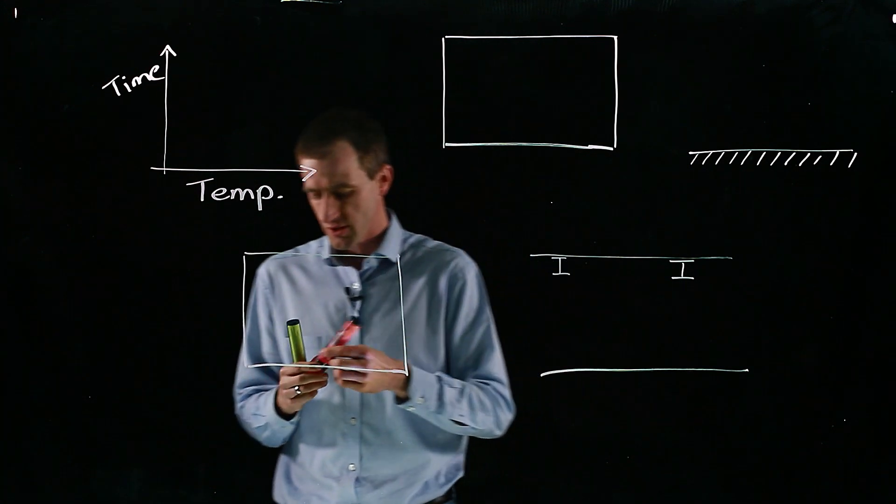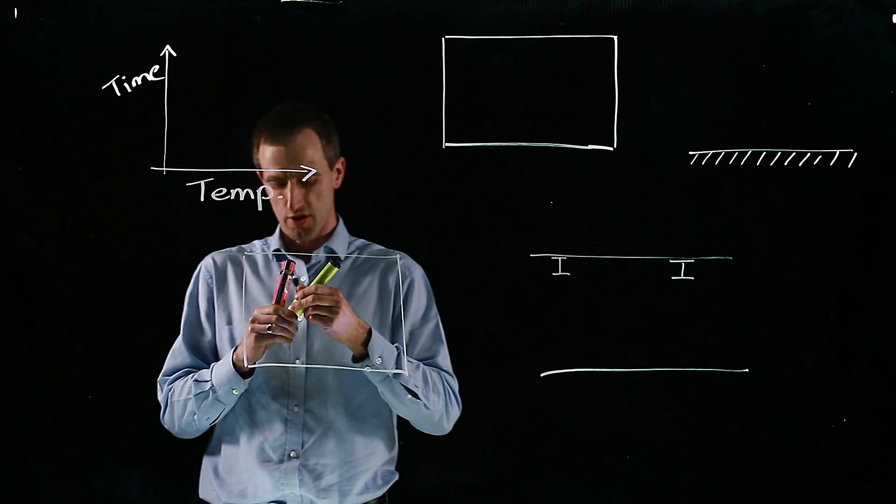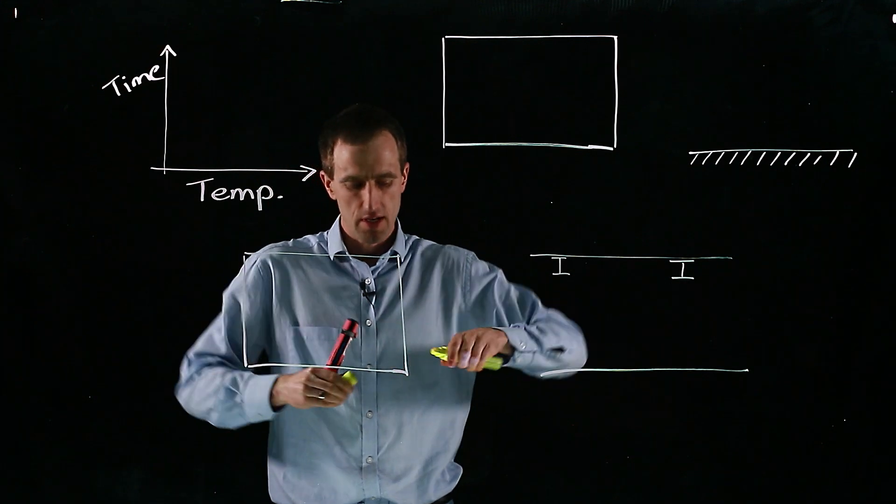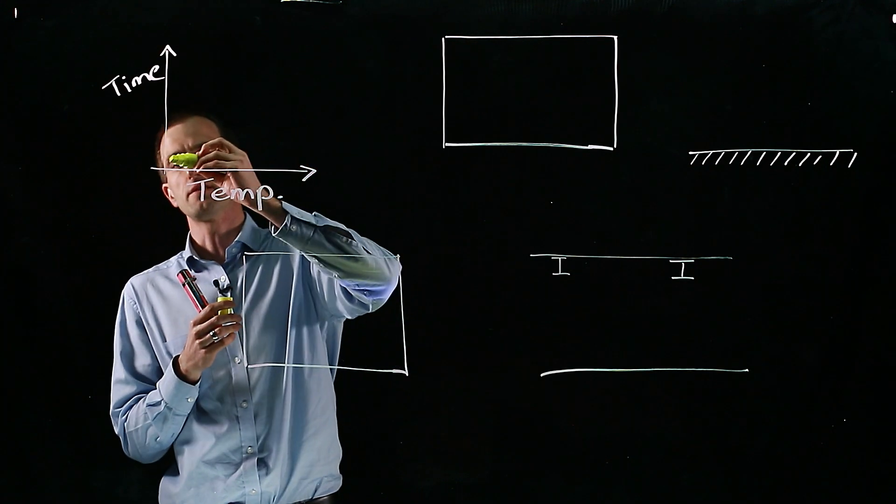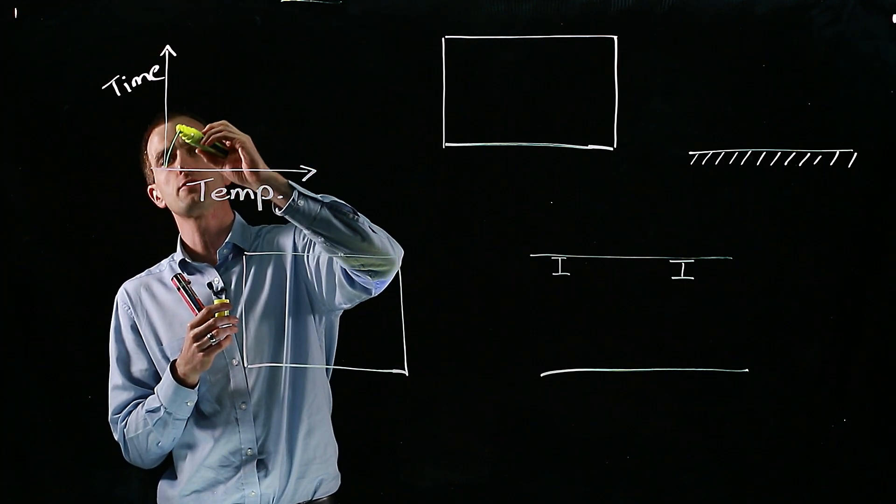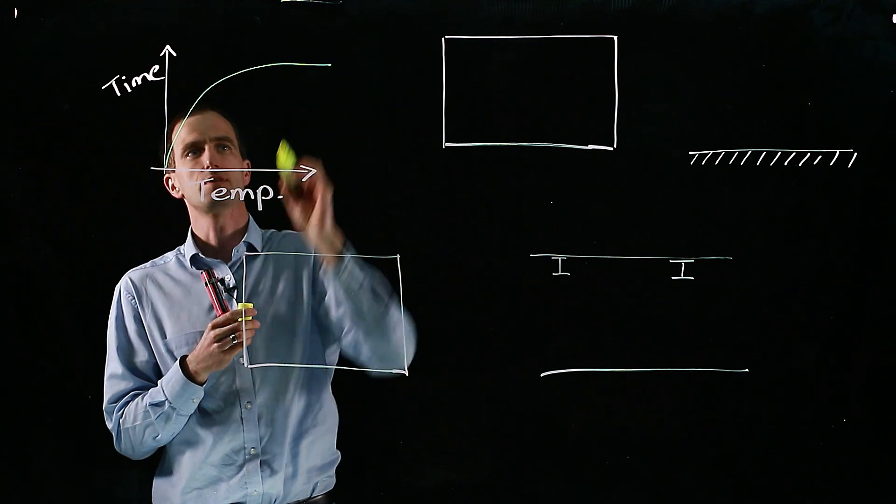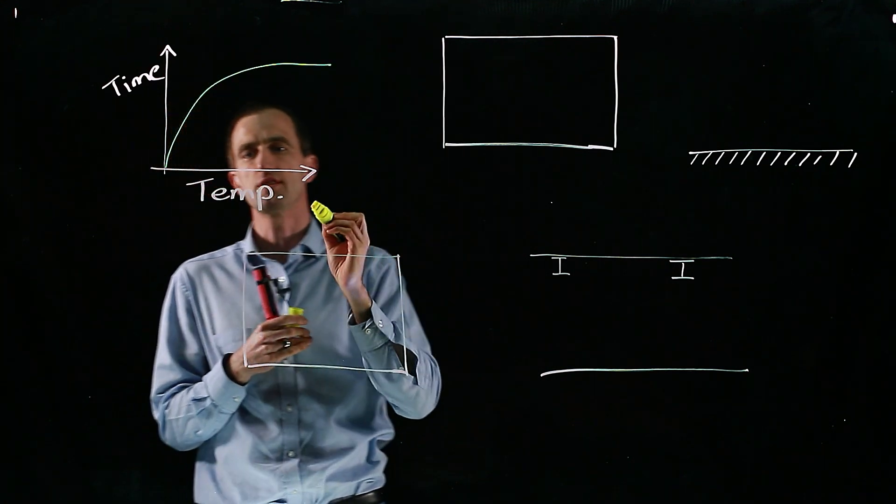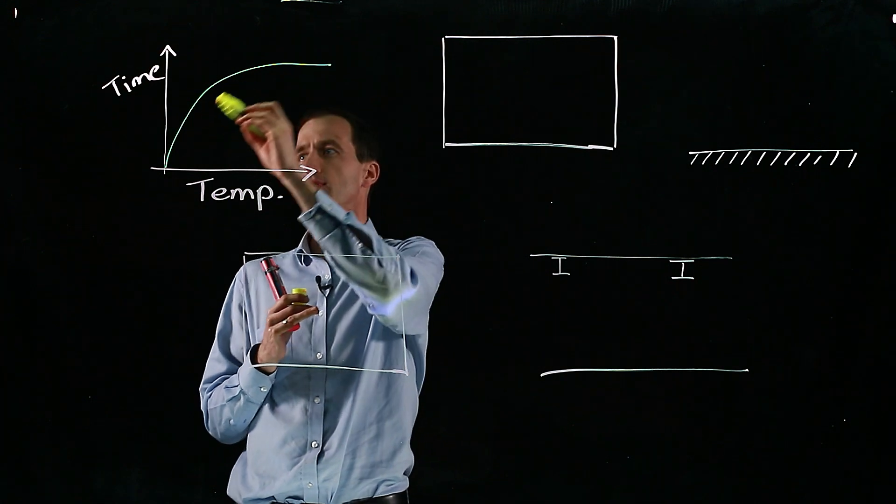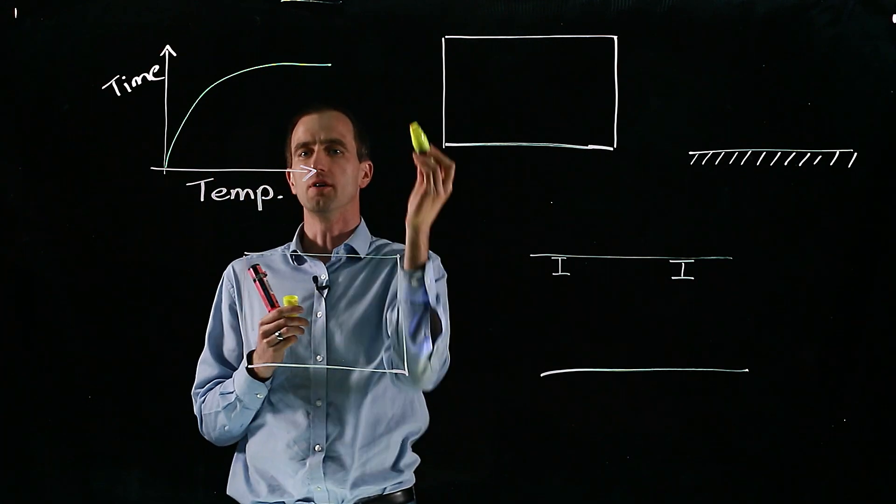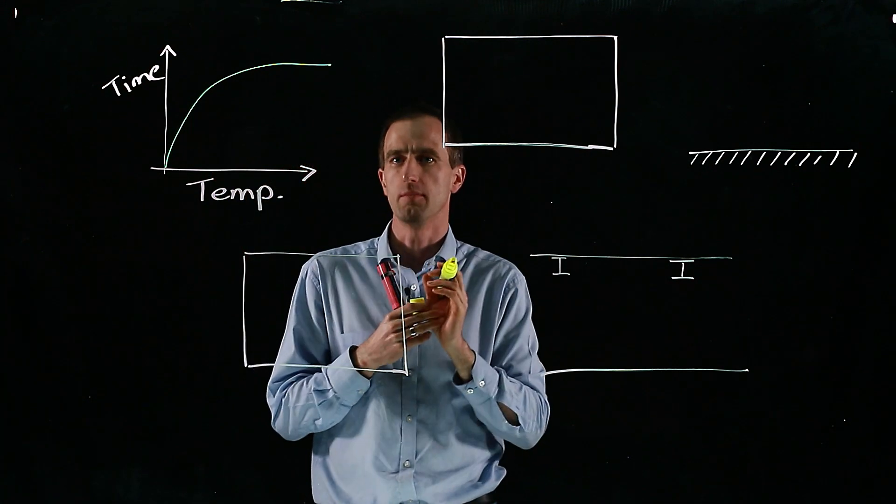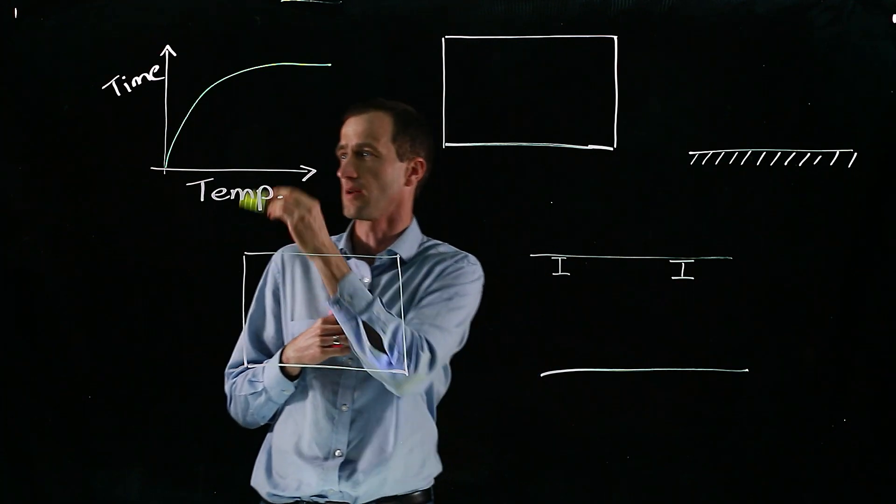Now we've discussed quite a lot the time-temperature curves that do exist. So the general one you'll use is your standard fire. That's the very most basic benchmark, a specific time-temperature curve that goes off to infinity. From that we can predict a temperature of fire with time with some well-established equations, and most of our furnaces use that.